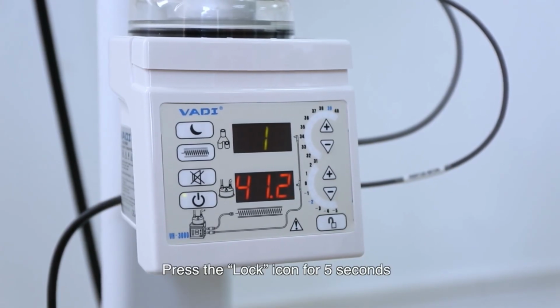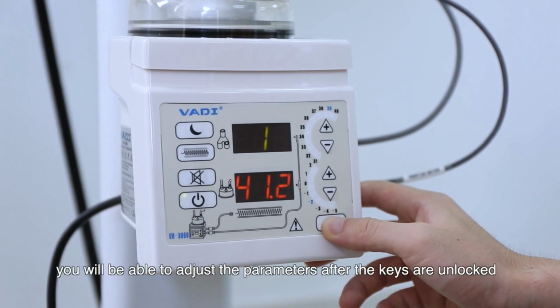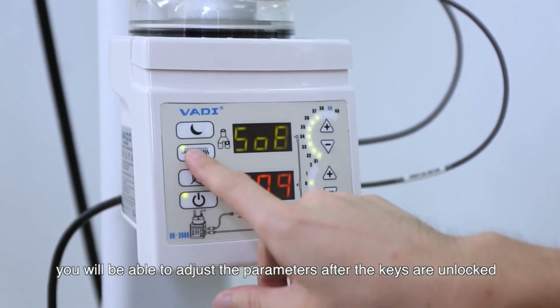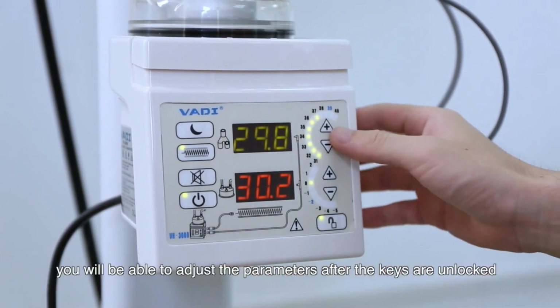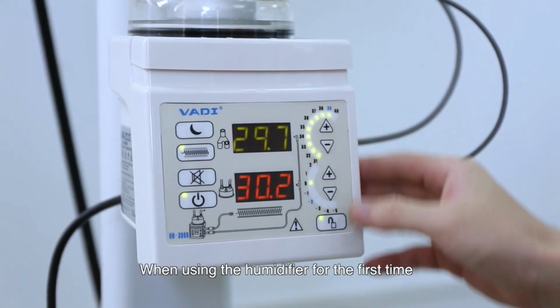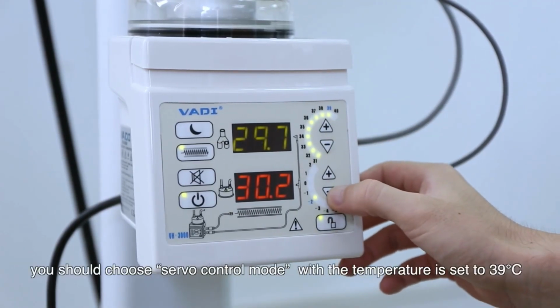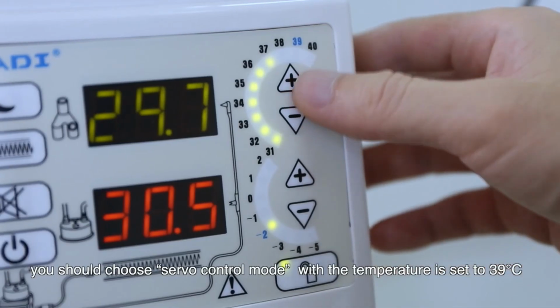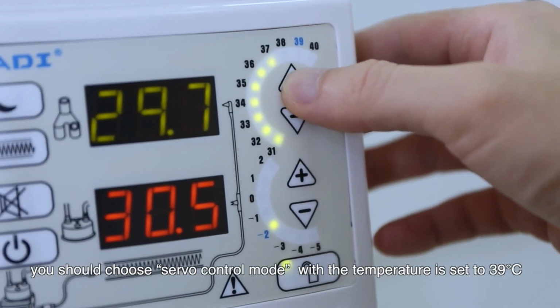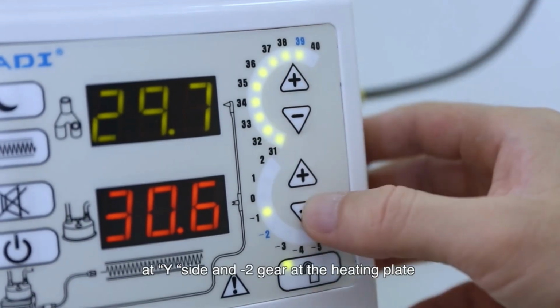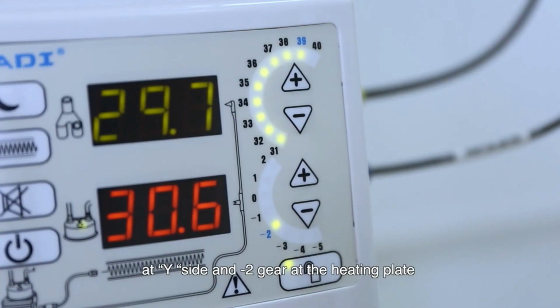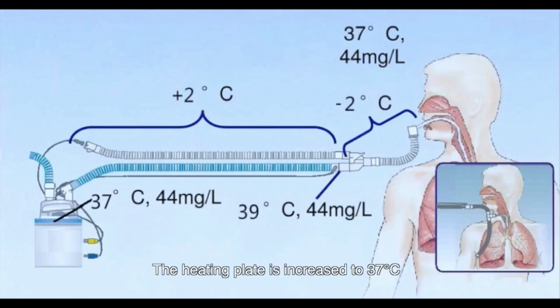Press the lock icon for 5 seconds. You will be able to adjust the parameters after the keys are unlocked. When using the humidifier for the first time, you should choose servo control mode, where the temperature is set to 39 degrees at the Y side and -2 gear at the heating plate. The heating plate is increased to 37 degrees.